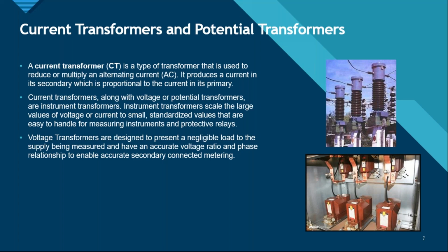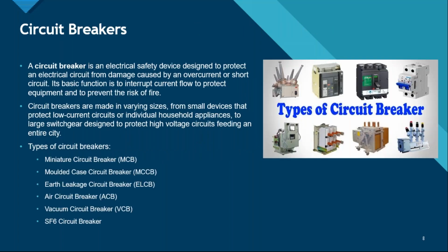Current transformers along with voltage or potential transformers are instrument transformers, right? Instrument transformers scale the large value of voltage or current to small standardized values that are easy to handle for measuring instruments and protective relays. Voltage transformers are designed to present a negligible load to the supply being measured and have an accurate voltage ratio and phase relationship to enable accurate secondary connected metering, right? All of the current transformers and potential transformers need to be inspected. They need to be tested as well. The ratio has to be checked, whether it is transforming the current or the voltage as per the ratio specified on it. All right. Then there can be circuit breakers.